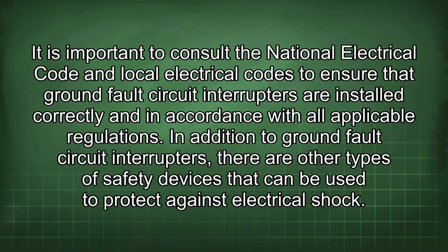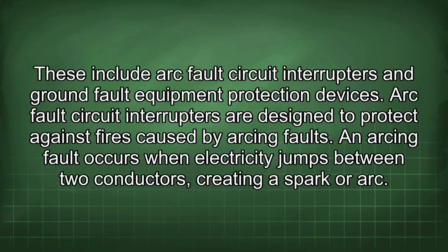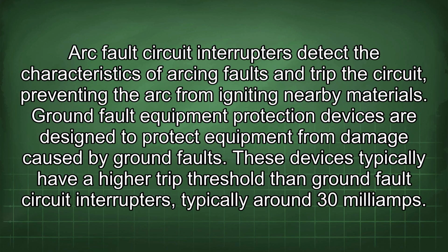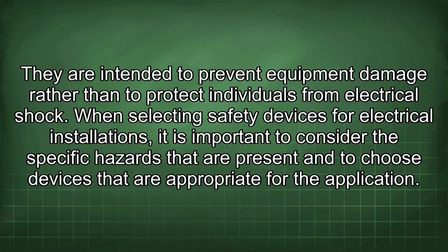In addition to ground fault circuit interrupters, there are other types of safety devices that can be used to protect against electrical shock. These include arc fault circuit interrupters and ground fault equipment protection devices. Arc fault circuit interrupters are designed to protect against fires caused by arcing faults. An arcing fault occurs when electricity jumps between two conductors, creating a spark or arc. Arc fault circuit interrupters detect the characteristics of arcing faults and trip the circuit, preventing the arc from igniting nearby materials. Ground fault equipment protection devices are designed to protect equipment from damage caused by ground faults. These devices typically have a higher trip threshold than ground fault circuit interrupters, typically around 30 mA. They are intended to prevent equipment damage rather than to protect individuals from electrical shock.